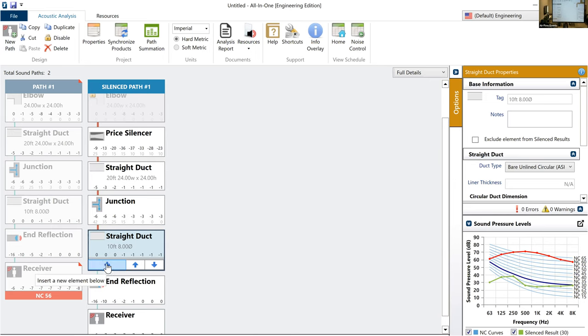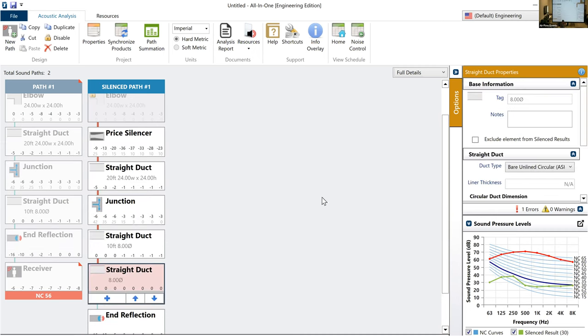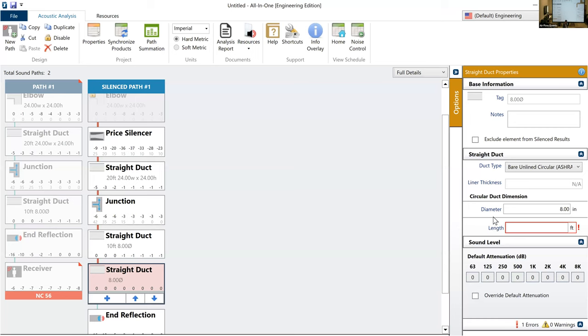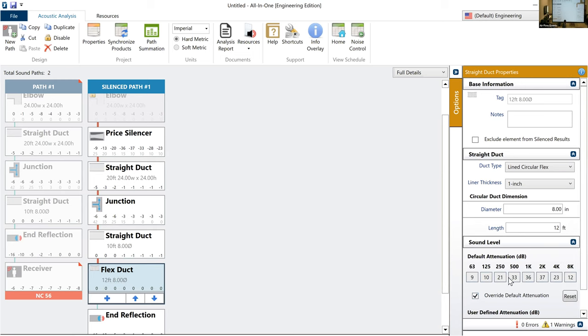Another thing I'll just quickly show is that we have a lot of acousticians that use this program, and acousticians, acoustical engineers, are quite specific with what they're recommending and analyzing. What a lot of large acoustical consultants will do is they'll have handbooks and tables and data that they've used for generations. And you can actually go in and say something like a flex duct that has a liner. If you don't like the values that are coming out of here, you can actually override them. You can go in and say, no, this is too much high frequency.